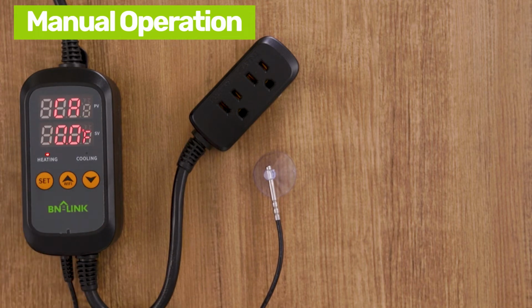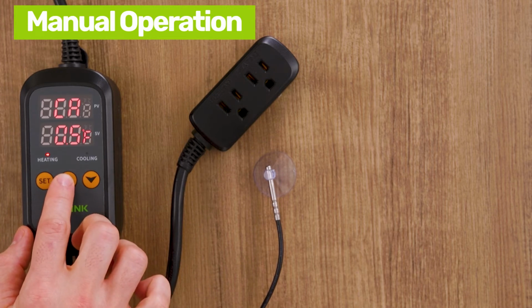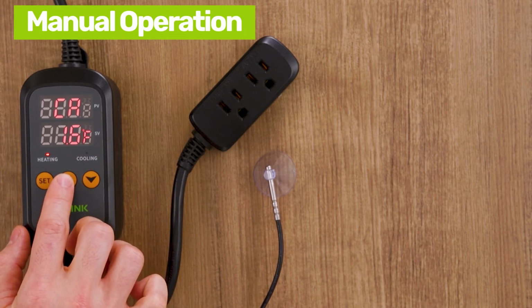Note that the rest of the menus are optional and not essential for the operation of the device. At this time, the device should be working properly. We will now go over the rest of the menus. After CD, or the cooling differential value, has been set, the CA will pop up. The CA menu is to recalibrate the temperature. For example, if the real temperature is 3 degrees higher, set the CA to 3 and the device should be calibrated.